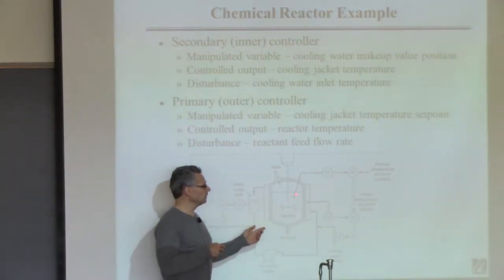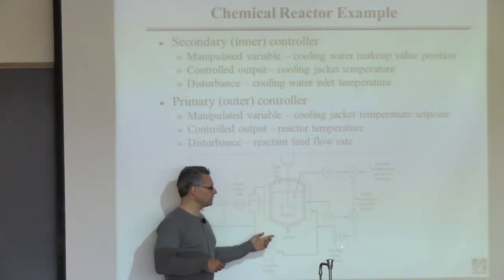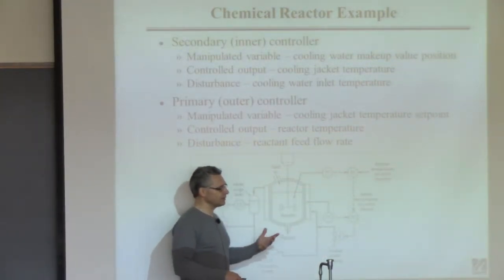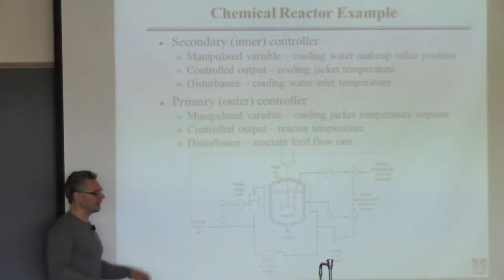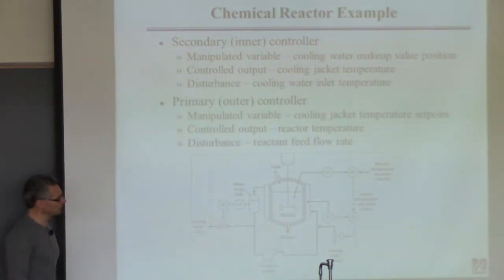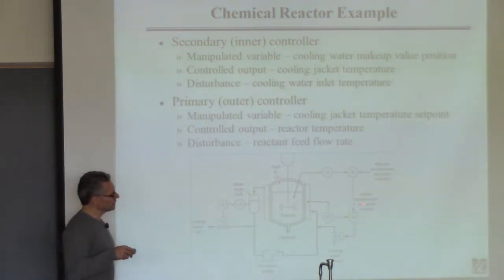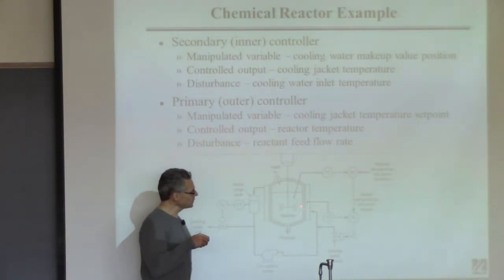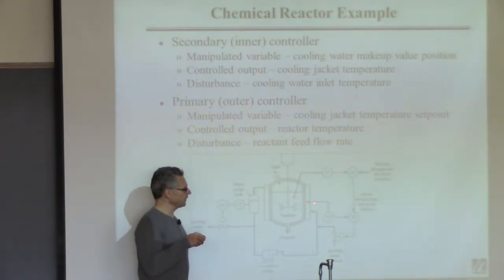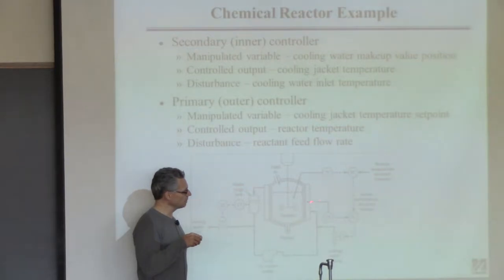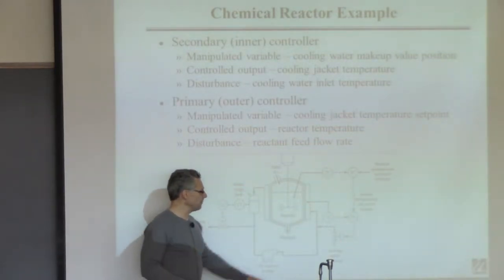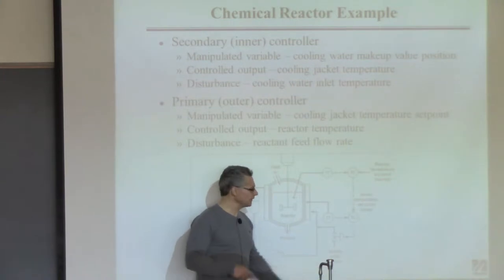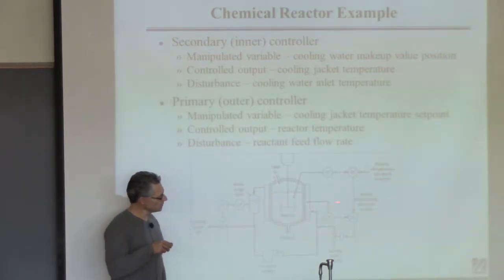Eventually we'll say uh-oh, we better change that, and we can change it but that'll take some time. It has to do with the residence time of the reactor. But an alternative strategy is to measure the cooling water itself — measure the temperature of the cooling water and try to control that. This controller measures cooling water temperature and attempts to control it by manipulating the water makeup. So this little controller just tries to keep cooling water temperature constant.